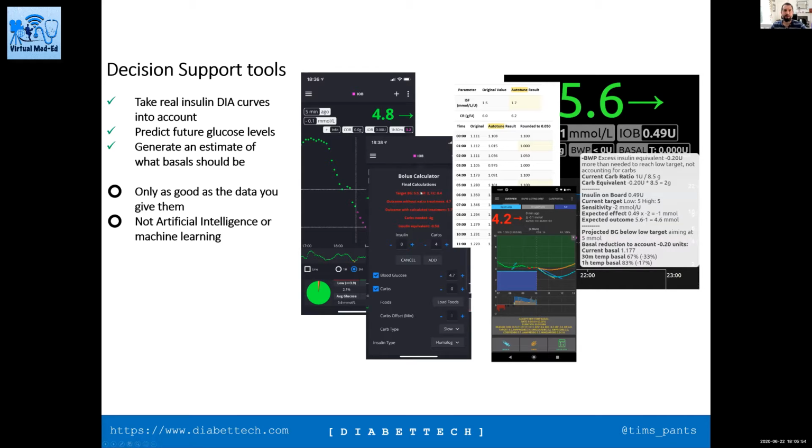The bolus calculators are also able to use that information to better provide bolus indications, and you can tell it whether you want it to take into account the blood glucose from the monitor, whether you want to take into account various other factors to generate a better outcome. In addition, there is a tool available that allows you to generate an estimate of what basal should be.